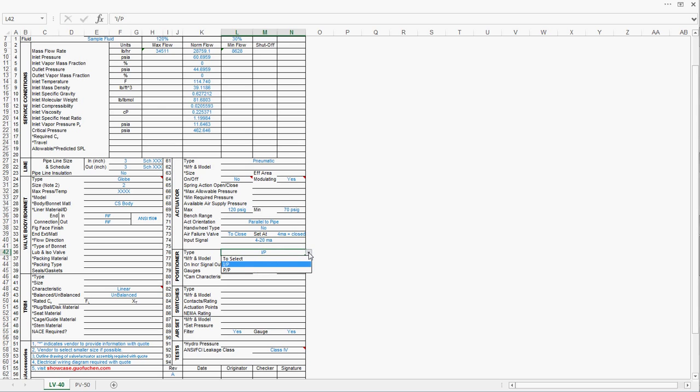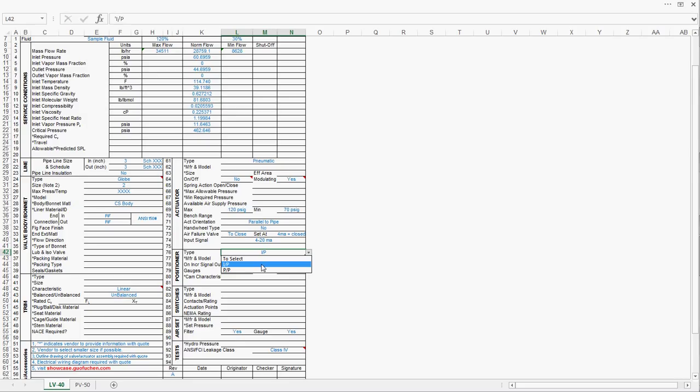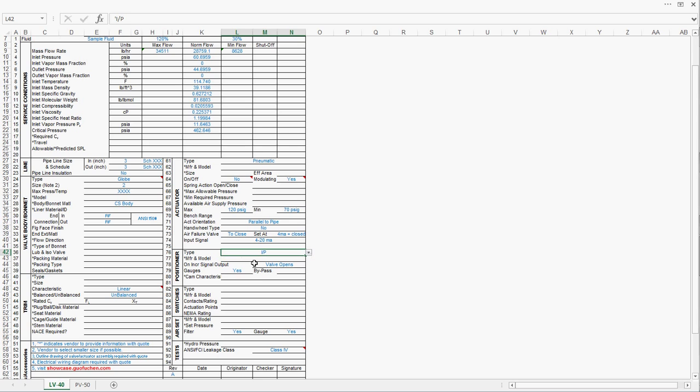Positioner. Two types: I2P and P2P. I2P stands for current to pressure. With the I2P positioner, the positioner converts the 4 to 20 mA into a desired pressure, and that desired pressure is going to drive the actuator to a desired position. While P2P positioner translates a pressure into another pressure that's going to operate the actuator to the desired valve position. Most of the time, we are using I2P. With the increasing signal output, most of the valves will start to open more. Generally, a pressure gauge will be very helpful to guide the user to better understand what's going on in that actuator.